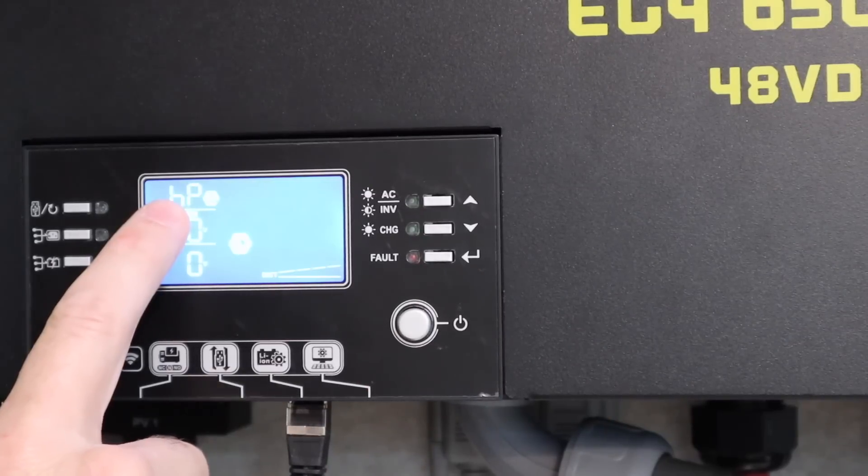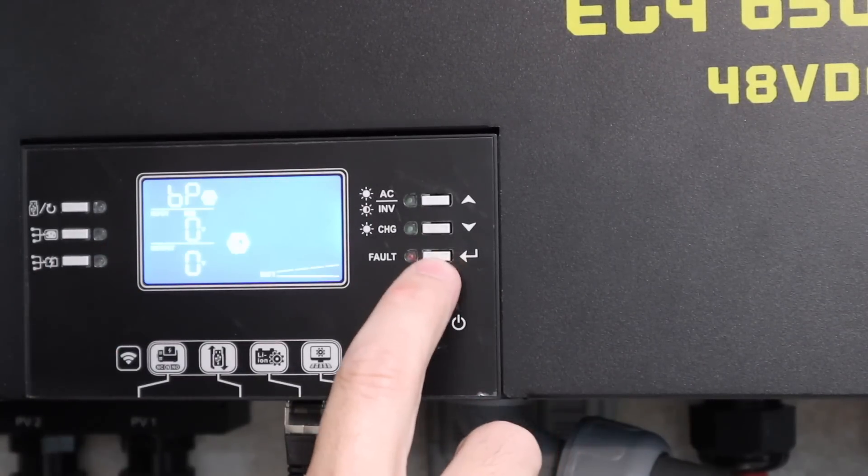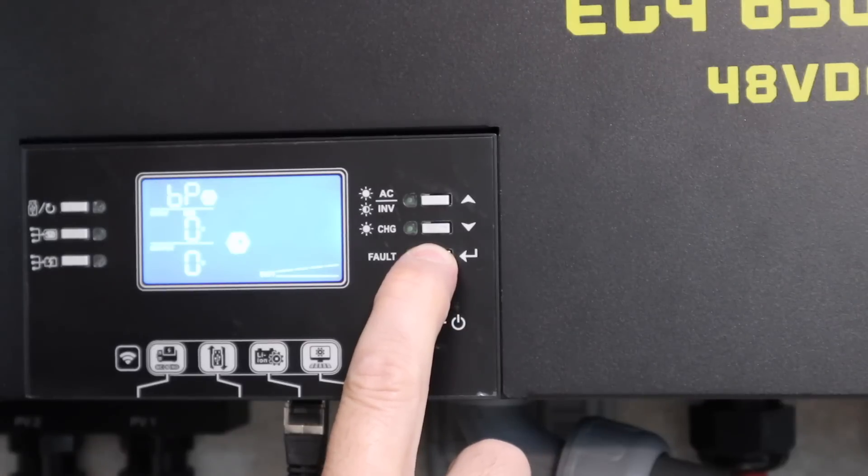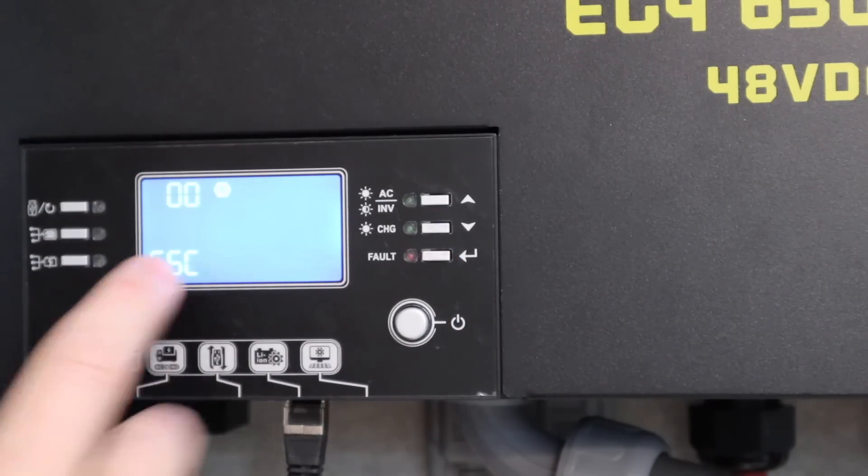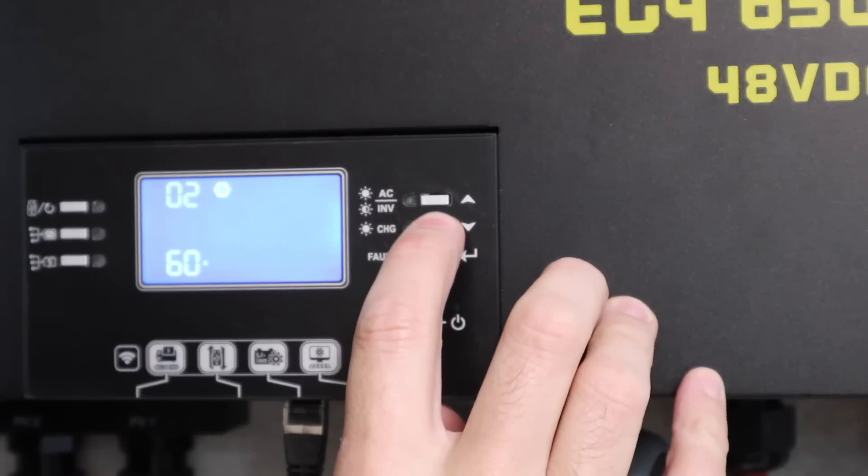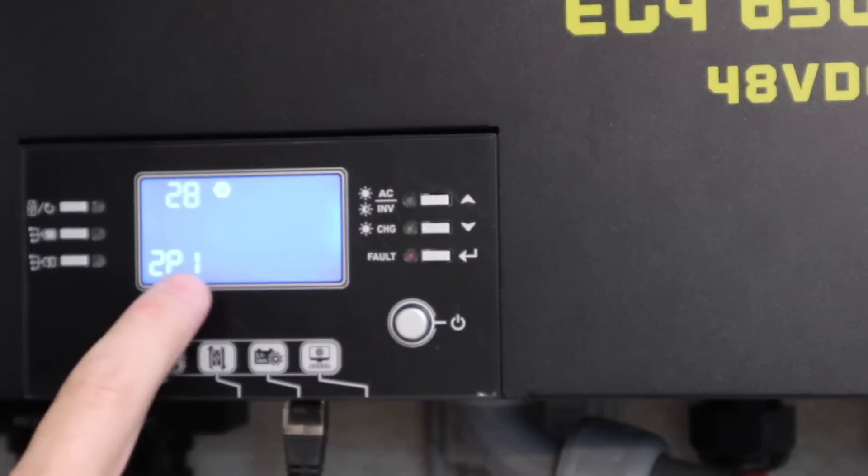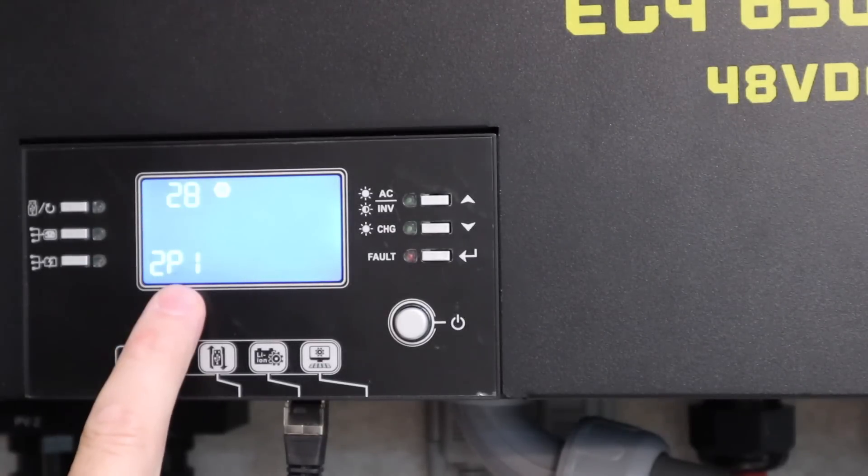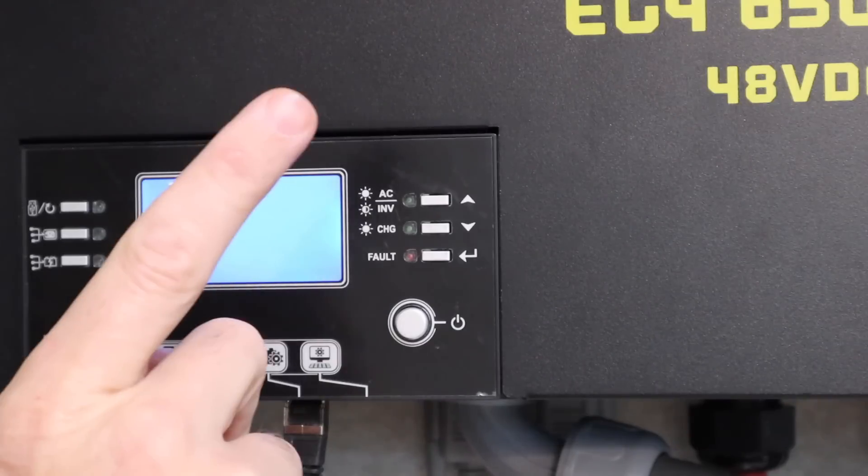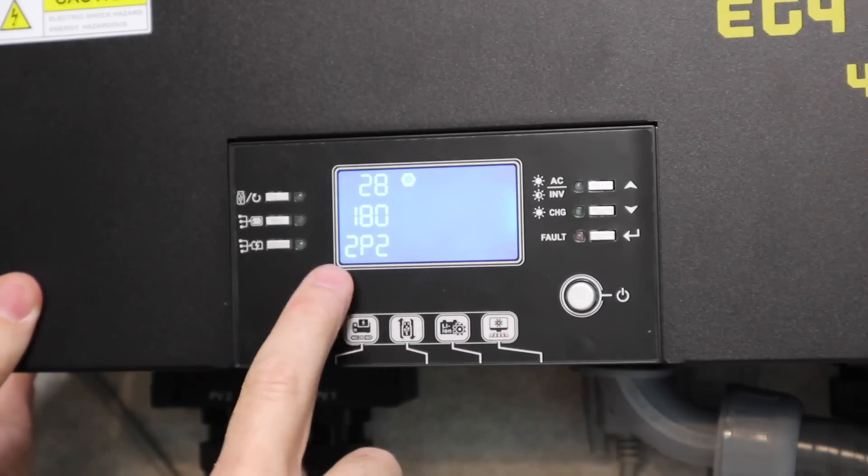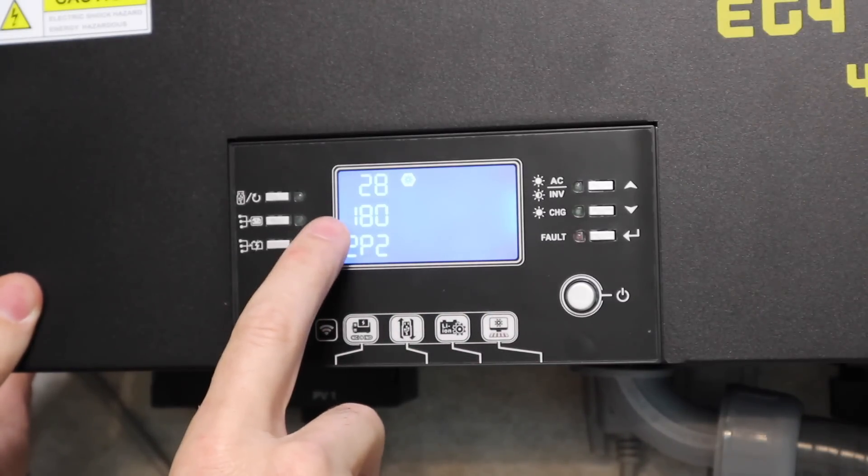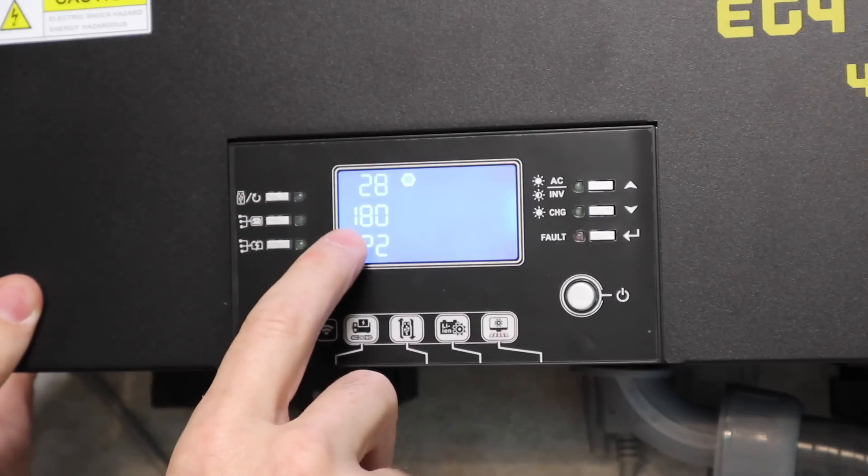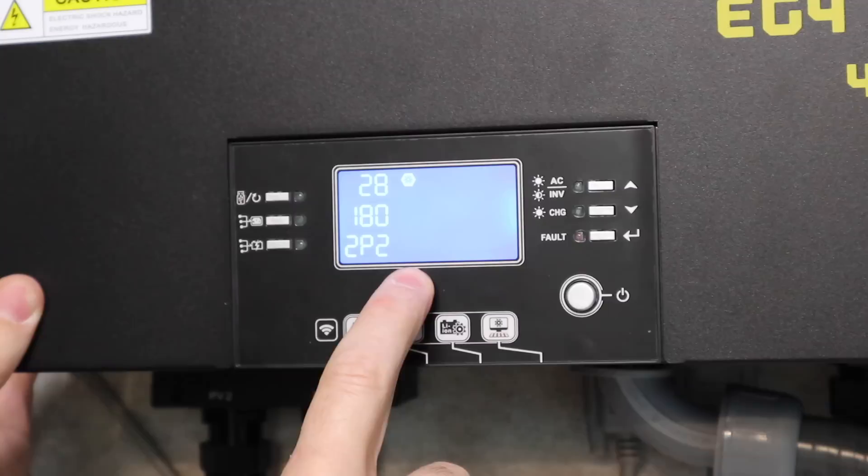We're going to go to protocol 28 first. This indicator here is telling me that I don't have any battery hooked up currently, which is correct. I'm going to go in the enter here. You can turn these beeps off later. Now we've got into our options menu. We're going to scroll down to 28. I've already done this, but we are going to set our master inverter as 2P1 and then we are going to set the other inverter as 2P2. This is our 2P2 over here and it's set at 180. So you don't know why it has a 120, but do not use the 120. Use 180 2P2.